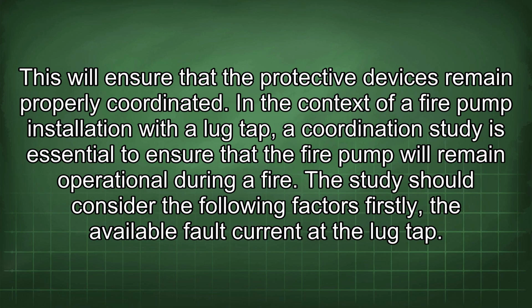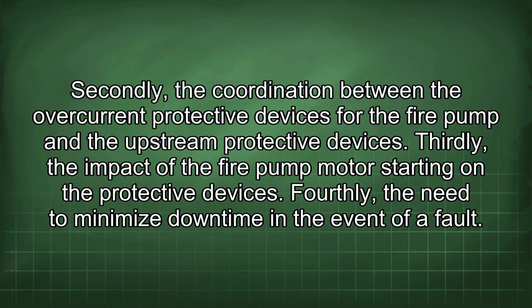In the context of a fire pump installation with a lug tap, a coordination study is essential to ensure that the fire pump will remain operational during a fire. The study should consider the following factors. Firstly, the available fault current at the lug tap. Secondly, the coordination between the overcurrent protective devices for the fire pump and the upstream protective devices. Thirdly, the impact of the fire pump motor starting on the protective devices. Fourthly, the need to minimize downtime in the event of a fault.